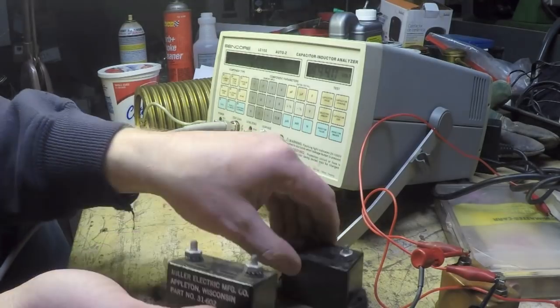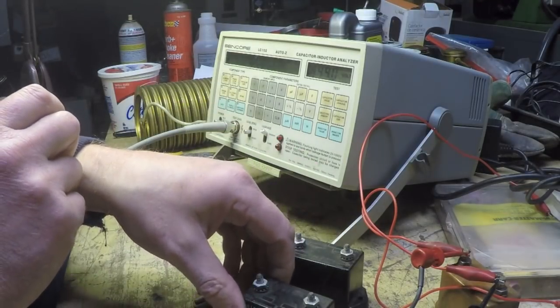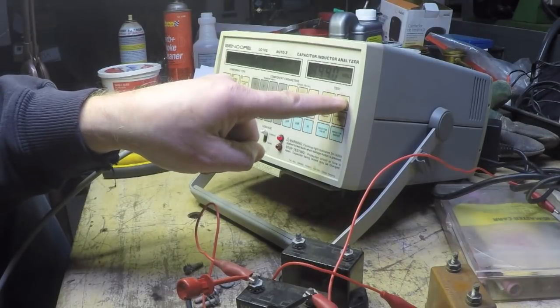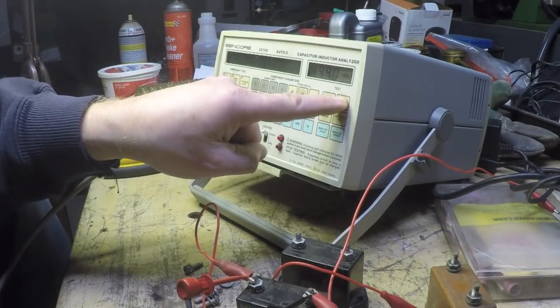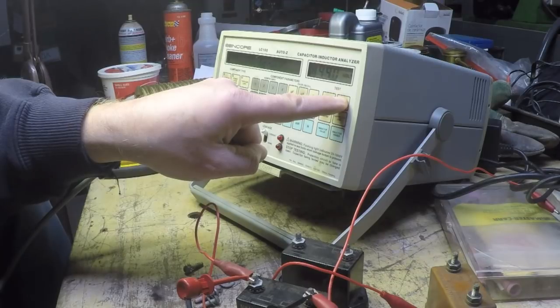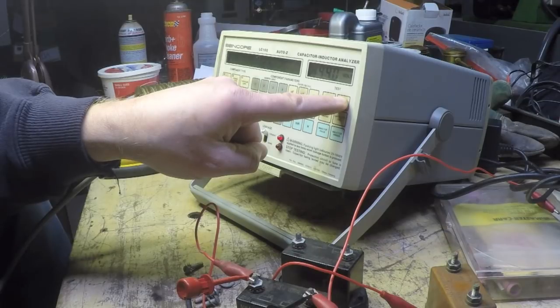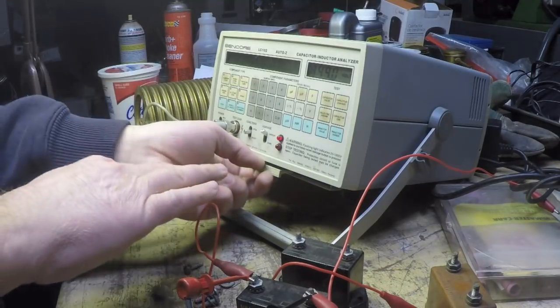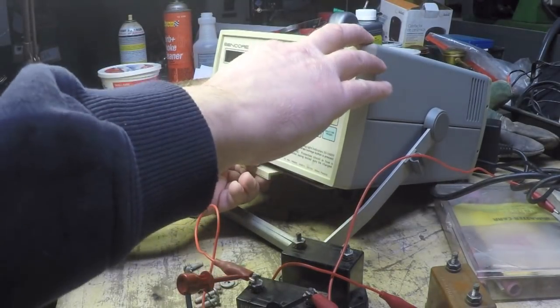But these have evidence of leakage. Just for the heck of it, let's see what these test. Value is good. This capacitor is actually showing 1.28 microamps of leakage, and it's pretty steady there, so I'd say this cap is leaky. Of course, I don't know what the allowable leakage current would be for a cap like this.